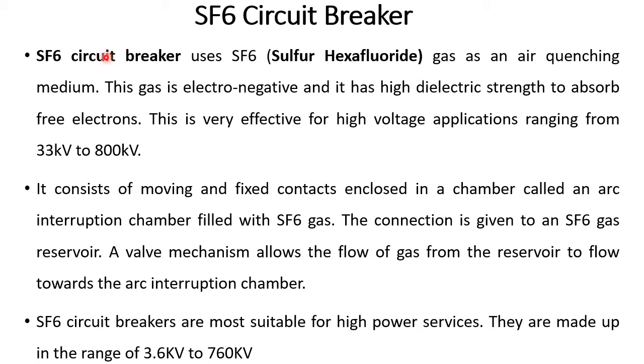SF6 circuit breaker. So SF6 means sulfur hexafluoride gas. It is exactly a gas which is going to act as an arc quenching medium for quenching the arc. This gas is electronegative and it has high dielectric strength to absorb the free electrons. So this is very effective for high voltage applications ranging from 33 kV to 800 kV.